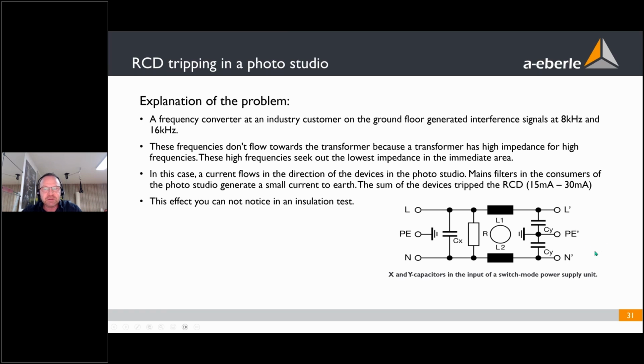The 16 kilohertz in the current going from neutral to earth, and the RCD, a 30 milliamp RCD, can trip beginning at 15 milliamps, and has to trip at maximum 30 milliamps. So if you have 20, 30 small devices and each input condensator takes 1 milliamp, then it's easy to reach the limit for the RCD, and the RCD is doing everything correctly. It has to trip at 15 to 30 milliamps.